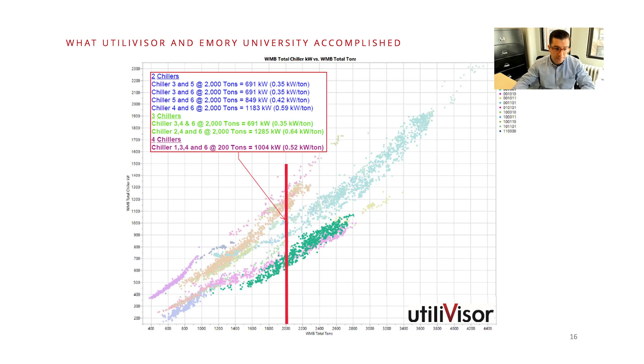So looking at those statistical formulas that we create, we create individual performance curves for each piece of equipment. So we know at specific loads, if I lower the condenser water temperature X amount of degrees, it's going to save a certain percentage for every degree lowered. On the bottom left, for this particular machine, the engineering is around anywhere from 1% to 2% per degree lowered. But with these constant speed chillers, sometimes we see it a little bit less. And actually, this particular one saved roughly about 1.5% for every degree. So again, getting better heat transfer with different cooling tower cells, we used a larger cell that we maintained around 70% flow. And we were able to say, okay, if you lower the temperature this much, we need to make sure that the cooling tower fan doesn't exceed X percentage, because then it's a wash.